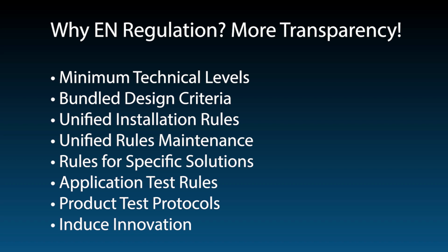I think particularly for the end users and the specifiers, it has been confusing and difficult to compare one system with another. Correct. So looking at the content and particularly the scope of the standard, we can see that it covers both low and high pressure systems. It covers local application, total flooding, and area coverage systems, a bit more like a sprinkler type design. But there's also a lot of information in the standard about the design, installation, operation and maintenance document. Yes, the DIOM we call it.